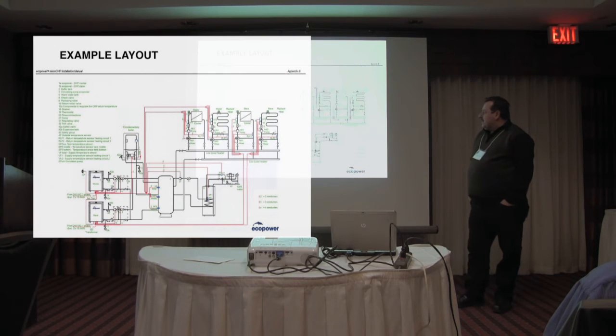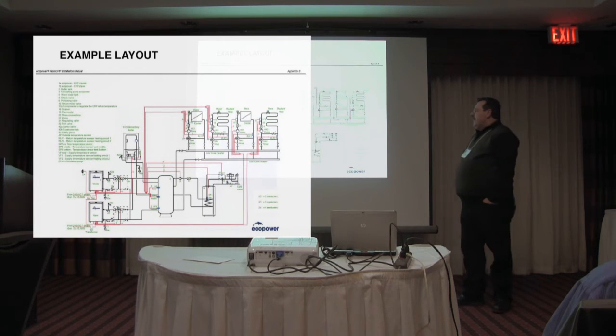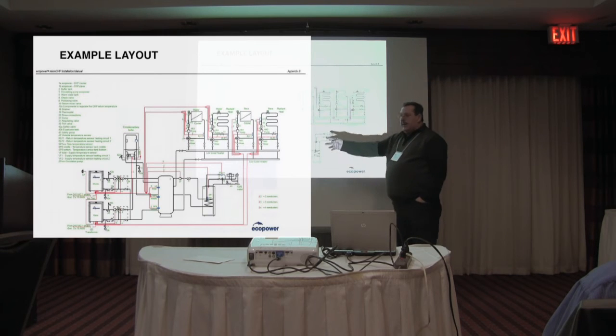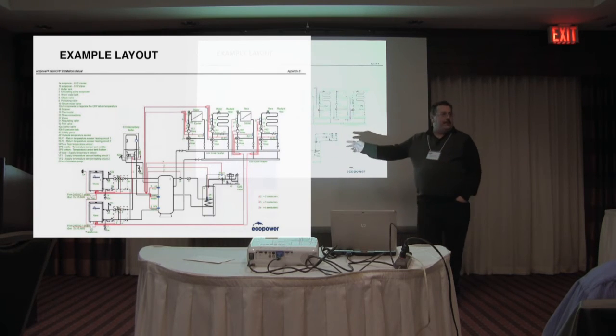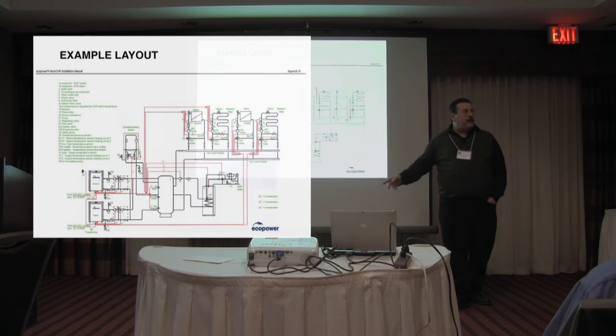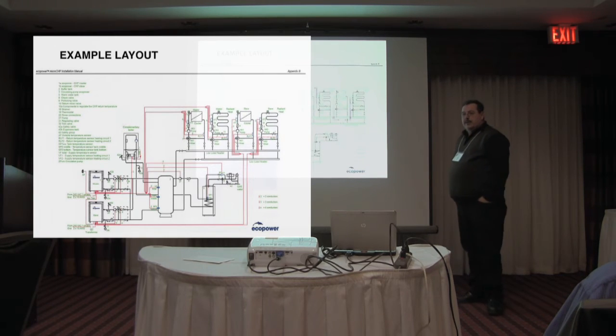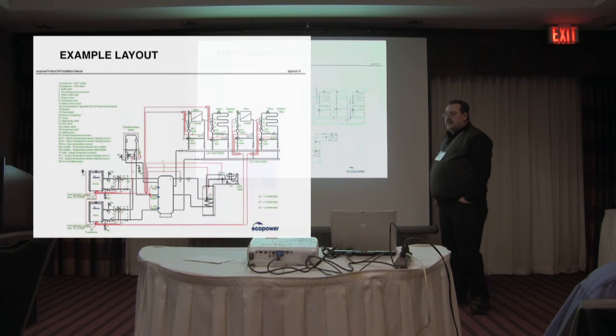You can parallel the systems as well. Here you can see, again, it's simply two CHPs, and there's a complementary boiler on the system. Always a good idea to have a backup source on that system. There are times where the CHPs, even though you have a lot of thermal mass, are still only putting out 80,000 BTUs. The difference here is you could be doing this 24 hours a day, 7 days a week. But there are times where the peak load is going to exceed the capacity of the CHPs, and you could have your boiler kick in to pick up that difference in temperature. So you set the design parameters for that.